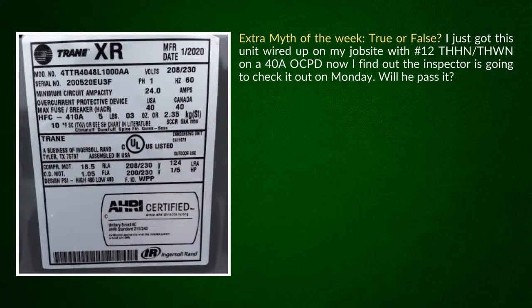Me and James have talked about this a lot. What happens is you go in there and the code gives you permission to go directly up to the 75 degrees C column, which is 25 amps. It says number 12 is good for 25 amps. Now, the one thing a lot of people miss on this is if you look at your full load amps, it's 18.5, and then you look at your fan load, that's going to be 1.01 or 1.05, something in there, which gives you right around 19.55 amps. And then they multiply by 125% for your continuous duty, and that's what gives you your 24 amps. So that 24 amp minimum circuit ampacity is with your 125% calculated in.